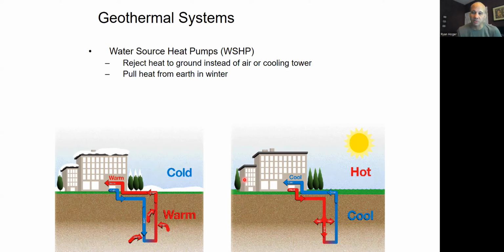However, it's very unlikely you put the exact same amount of BTUs in the ground as you take out of the ground. So one of those seasons is typically more dominant. Let's say you're cooling dominant. You're shoving more heat into the ground all year than you're taking back out the rest of the year. Well, then come next summertime, instead of starting out with 60-degree ground temp and heating it up to 80 over the course of the summer, now I'm starting at 62-degree ground temp, heating it up to 82. And then the next year and the next year. And then eventually at some point it's too warm. It becomes a problem, right?